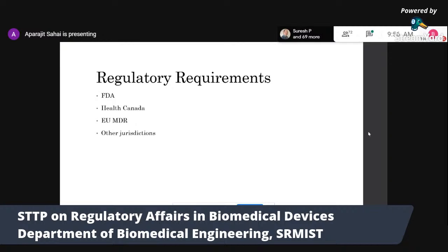But if you are manufacturing a much lower risk device such as an ultrasound device, you can essentially put your device on the market without complying with 21 CFR Part 820, but within 2 years you will need to. If you're manufacturing a low-risk device, the FDA is not going to come and audit you in the next 2 years. They say they can, but they're not going to do that. So you have 2 years to implement a quality system.